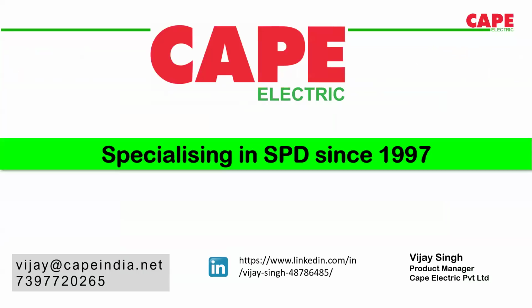Now, as Mr. Anandu very well said, the backup protection in an SPD is a very important subject and it's also a very confusing subject. A lot of people don't know what exactly they need to use as a backup protection. People are still confused between fuse, MPCBs, MCBs, what they have to use and what rating they have to use. So I'll go into detail on why exactly we need a backup fuse.